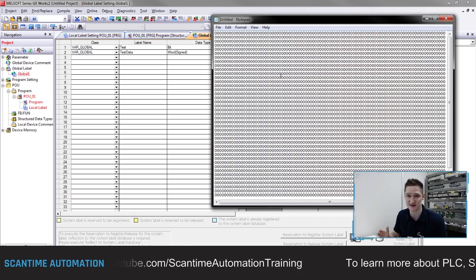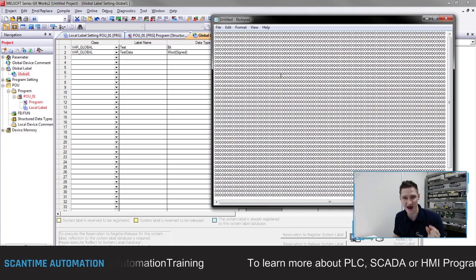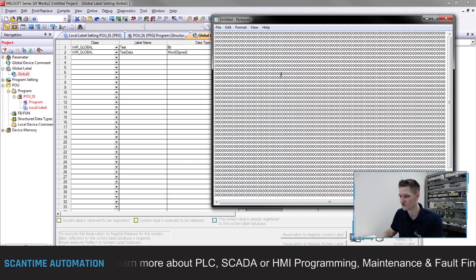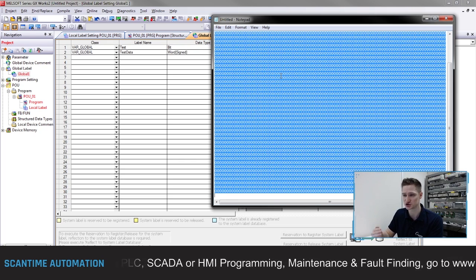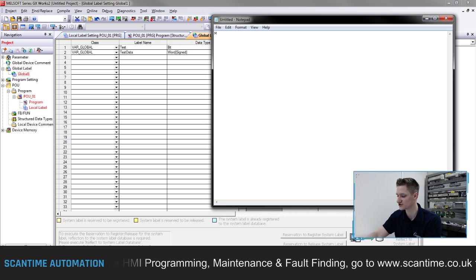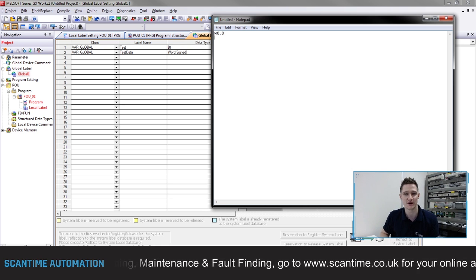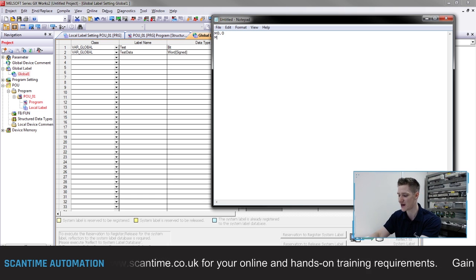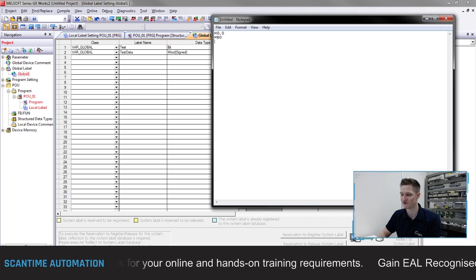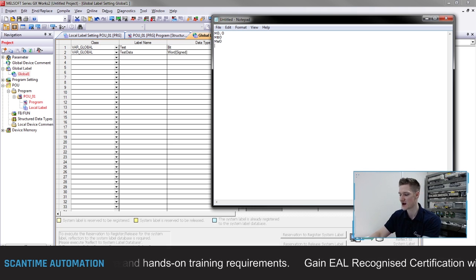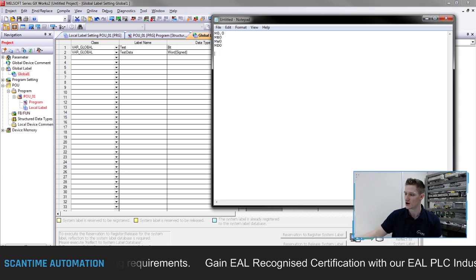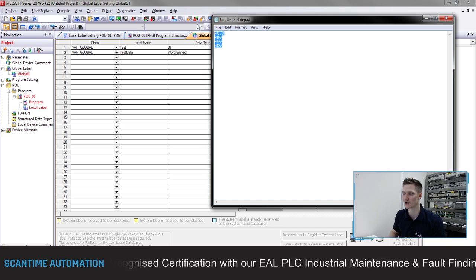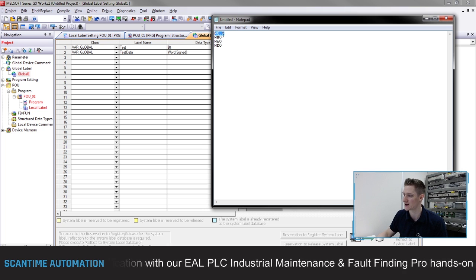For Siemens, they use the term M to identify an internal register. Depending on what you're wanting, if I just want an internal bit that goes from logic zero to logic one, I would use M0.0 - that signifies an internal bit. If I wanted a byte, a collection of eight bits, I would choose MB0. If I wanted a word that would be MW0, and a double word, which is 32 bits, would be MD0.